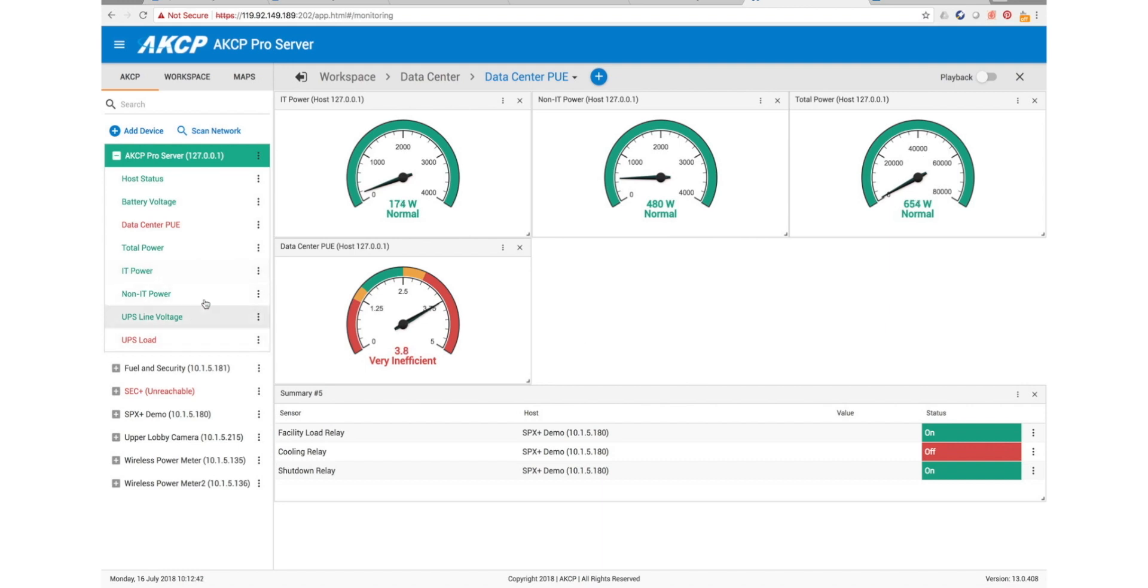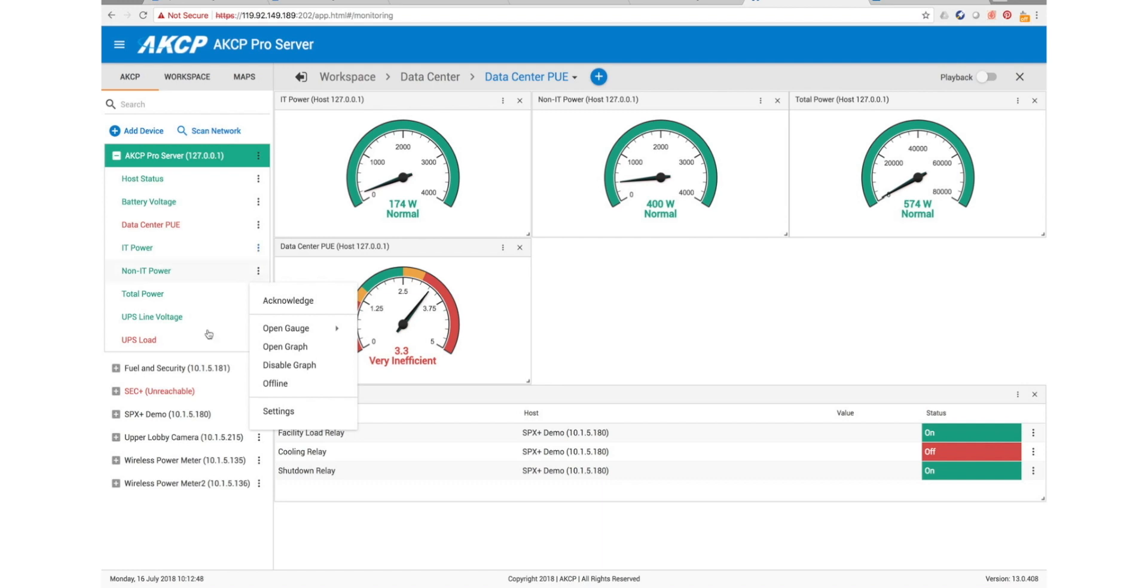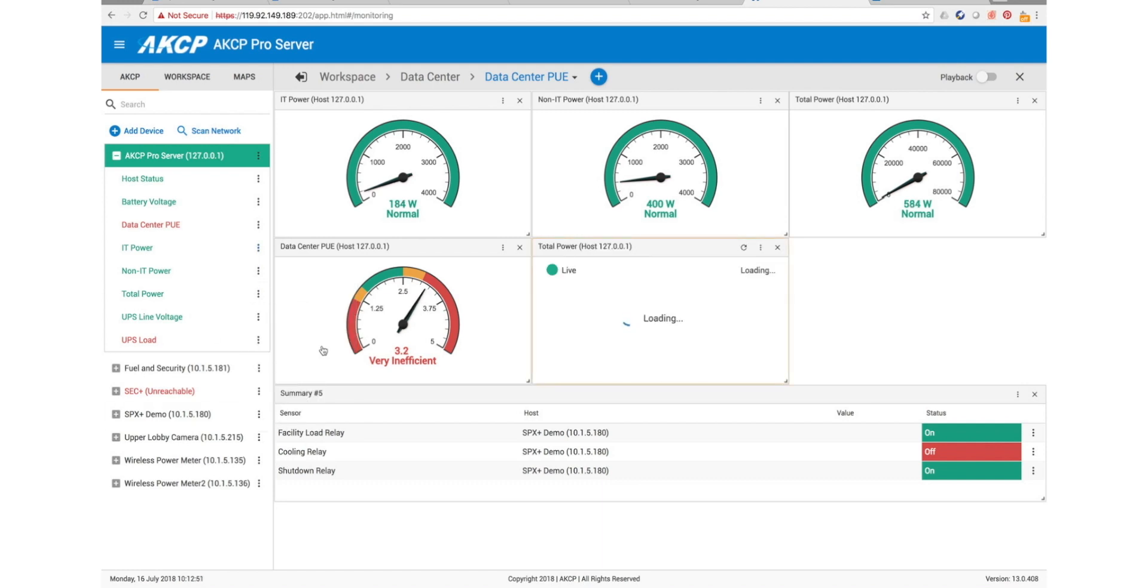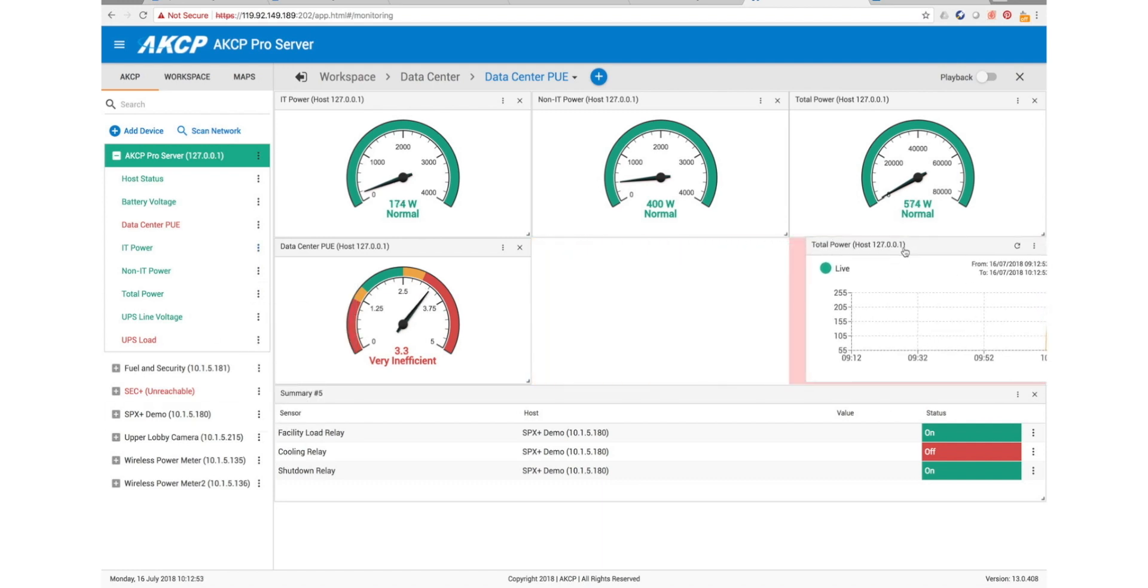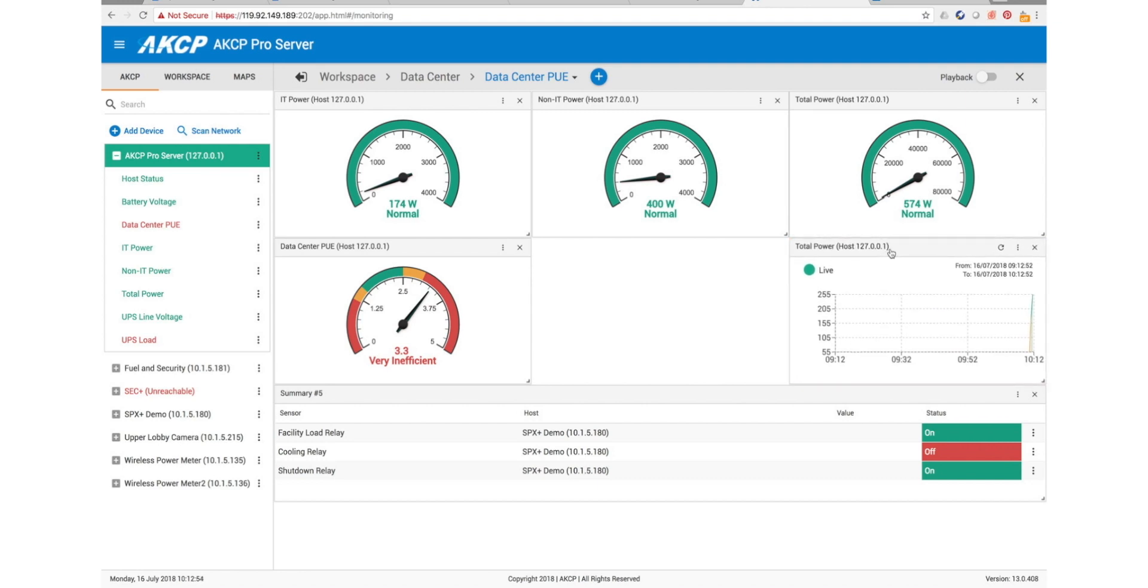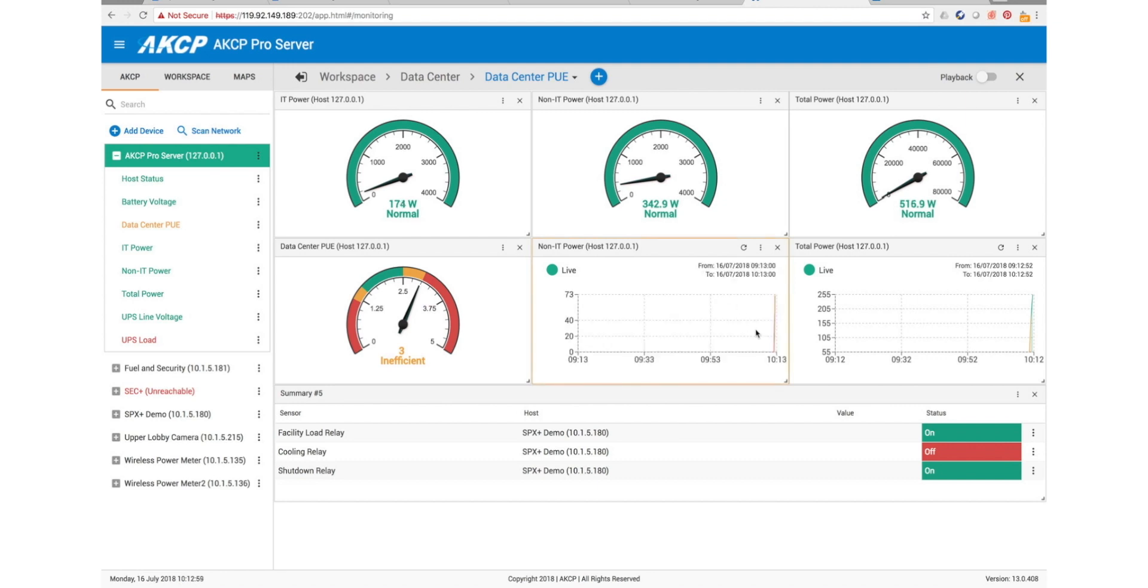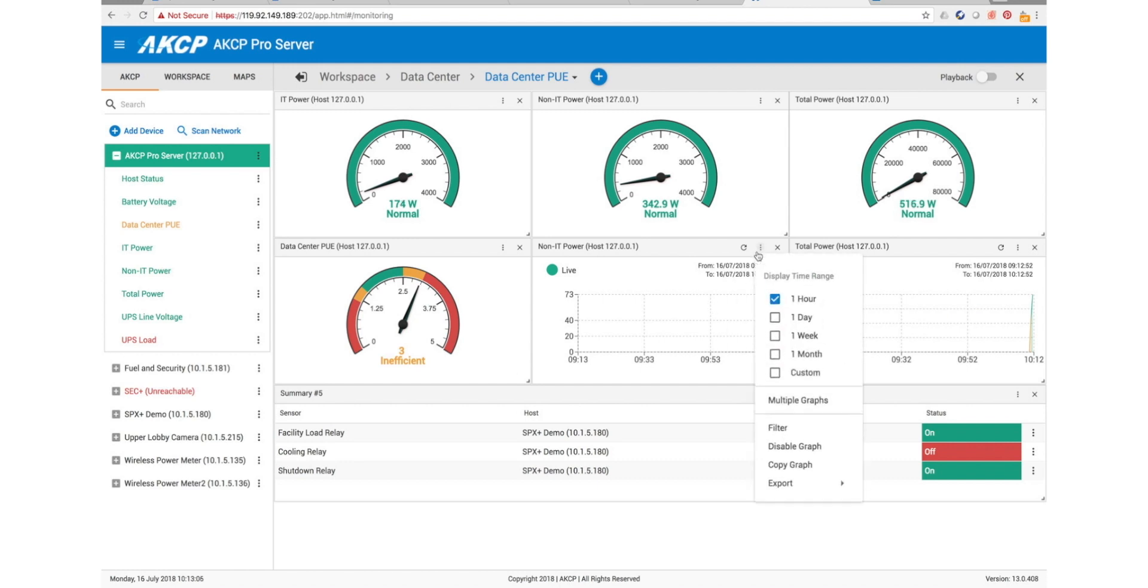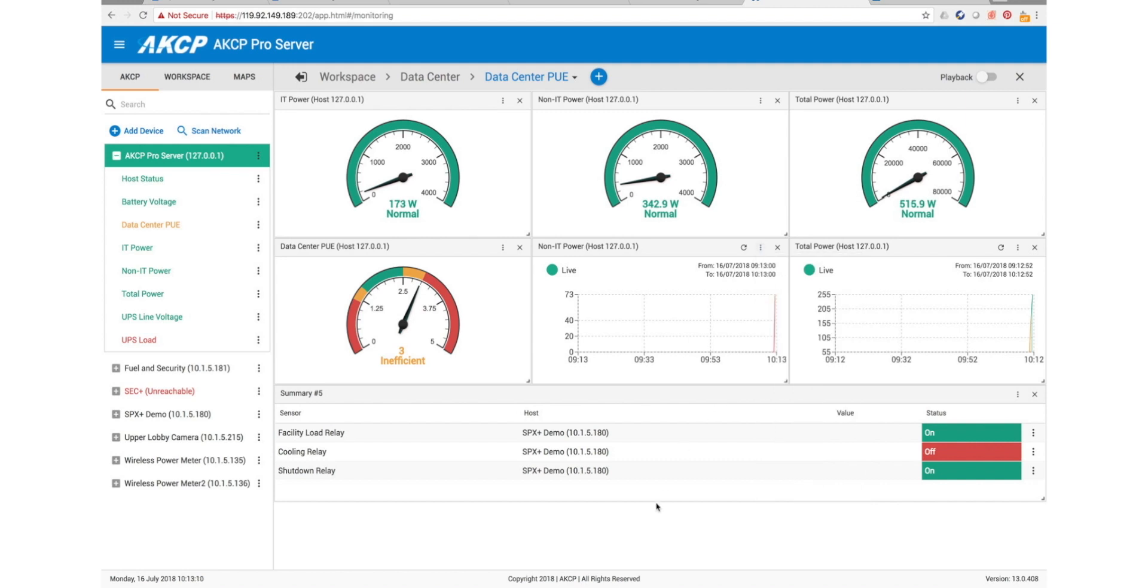The final thing I want to add into here is our graph. We will put in a graph of our total power, so we just go to open graph. We'll also put in a graph of our non-IT power. These will now begin graphing over a period of hours, or we can change this to days, weeks, or months. We can choose the scale of the graph here. That's basically how we set up our PUE virtual sensors here in AKCP Pro Server.